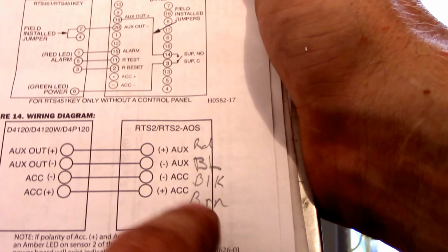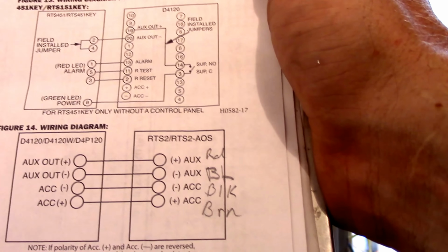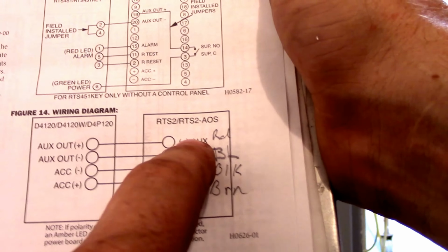You got red, blue, black, and brown. You got positive auxiliary, negative auxiliary - this equipment's going to be running off of DC power. Then you got accessory, which is a signal, and accessory, which is another signal. These are not direct connection power - these are signaled by the control modules inside on the walls for the smoke alarm.